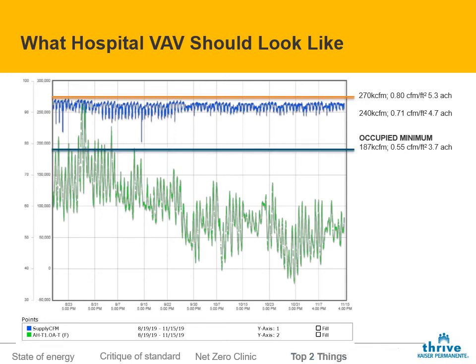In an average hospital building, this is a full-blown hospital patient tower, by the way, you should see a code minimum that's about 0.55 CFM per square foot, or just under 4 air changes for the whole volume of the building, right? In California, that's a little bit lower because of the patient room thing, but only by a marginal percent or two. That's the daytime code minimum.